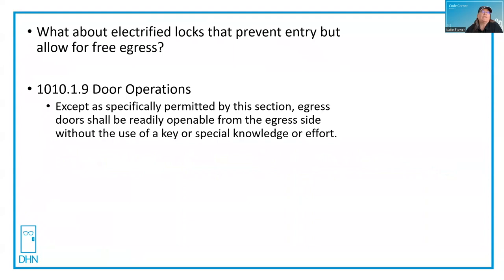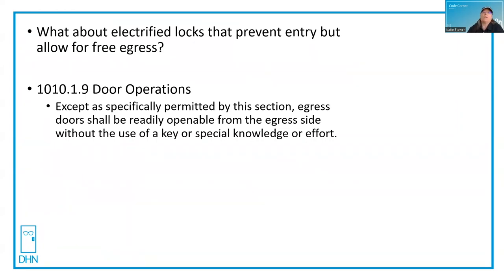But what about electrified hardware — the locks that prevent entry but allow for free egress? Access control can be confusing to AHJs, and some will say that any door that has access control for entry must also meet UL 294. That's not true, unless you're locking the egress side, and that's covered by those special locking arrangements.